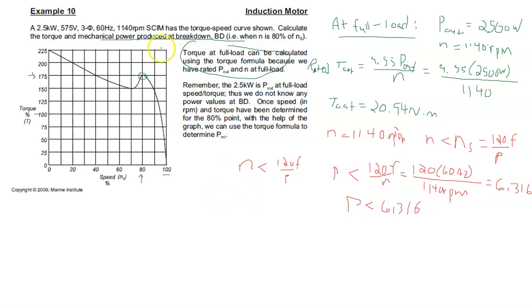So we know that p is less than 6.1316. Remember, p is poles per phase. And the fact that this is a squirrel cage induction motor means p must be equal to 6 poles per phase. Then our calculation for Ns, 120 times f divided by p, gives us 1200 RPMs.